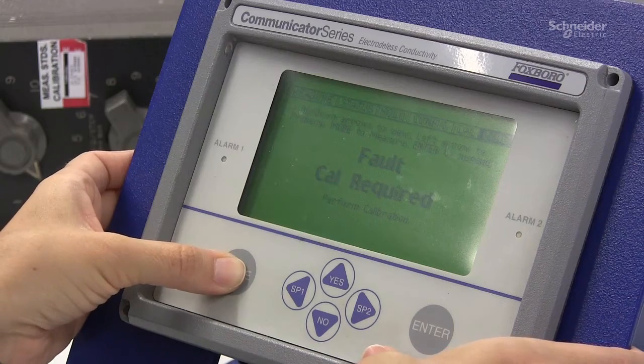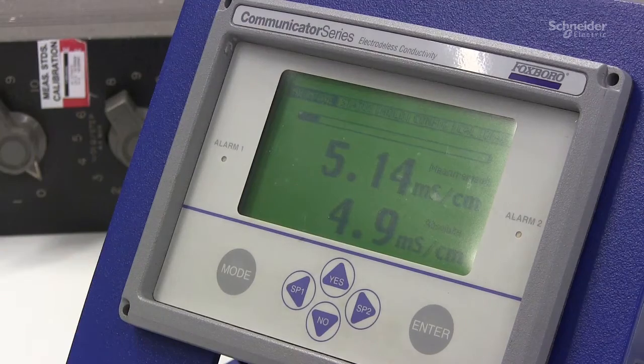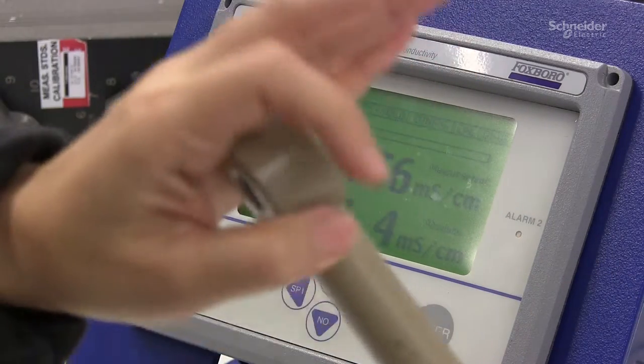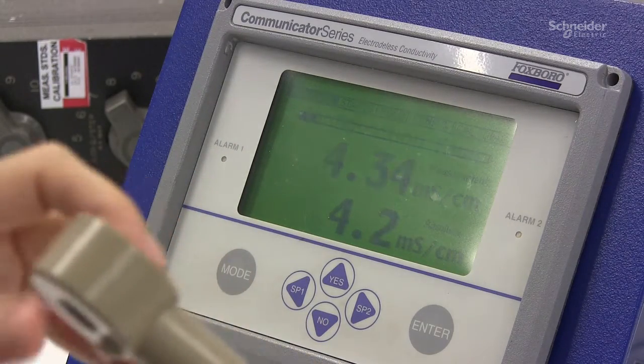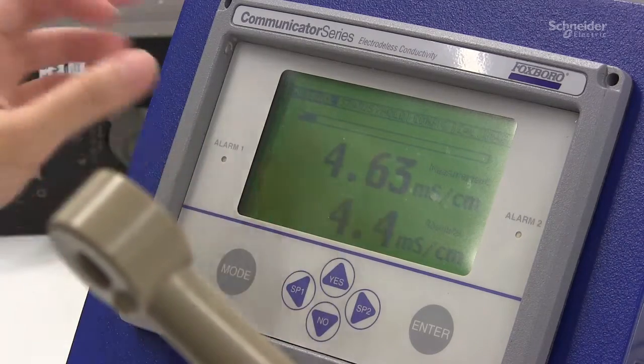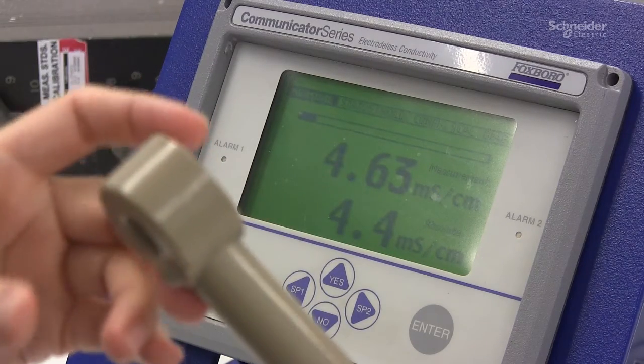So press mode again to go back to measure mode. If you see right now we have the sensor on the bench with nothing connected to it which should be giving us a clear zero and it's not, it's deviated. So we will proceed with the calibration now.